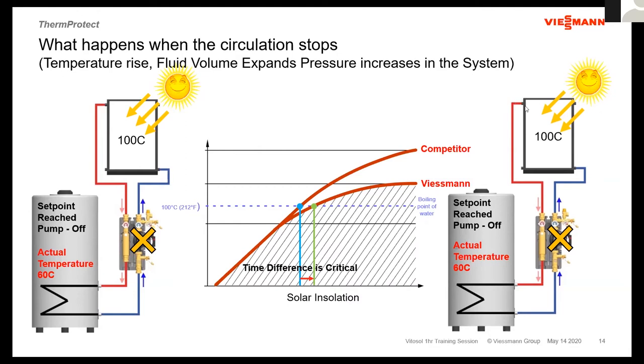You would have a sensor, ideally in these collectors, sitting up right in this area, picking up that hot temperature that these collectors are sitting at. On the opposite side, the sensor we're reading in the storage tank, we're not going to be reading a sensor up here. That's not a good position for a sensor in a domestic hot water tank that's being controlled for solar. We don't even want it in the halfway point.